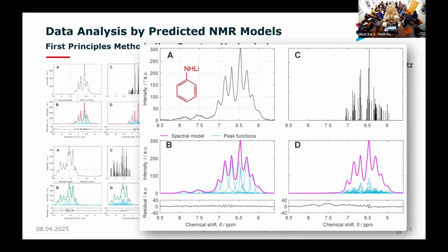So what we try to do is get our pure components into a kind of database and then click together the mixture model on the fly, because a lot of chemometric modeling is very tedious when it comes to calibration. You need to start from scratch. If you change something in your process, you need to go all the way back to the front and do some new modeling. This is where indirect hard modeling is very nice, because you basically combine components, and for example, if you find a new component, you just add it to your model later on.